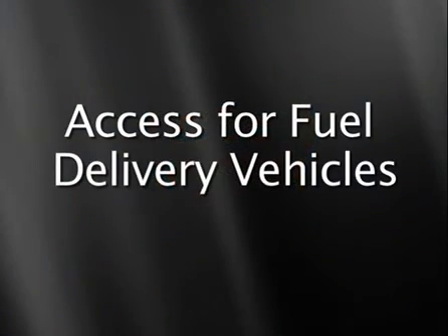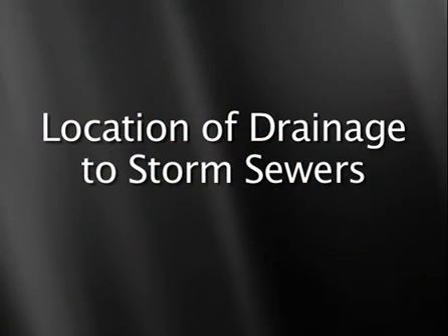An above-ground tank at grade adjacent to a building will look as good as a tank can look. For that reason, they are typically enclosed by architectural walls or fences. The tank needs to be located so that a fuel delivery truck can drive adjacent to it for filling, although remote fill stations can be used if this is a problem. The tanks and fuel delivery area is designed to be separated from the storm drain inlets to allow any leaks or spills to be cleaned up before flow to storm water systems.